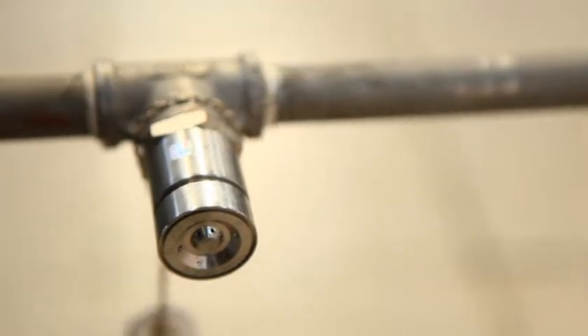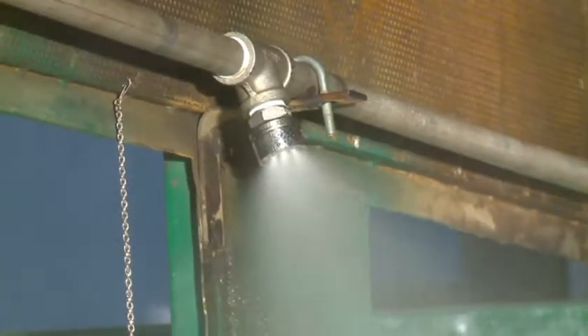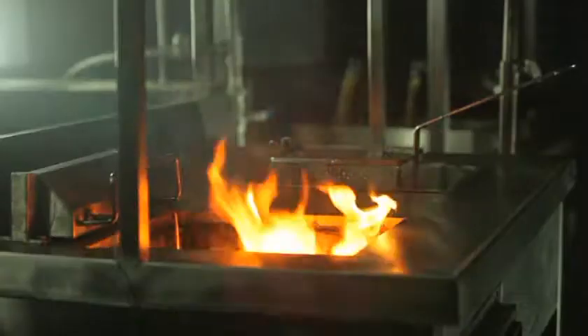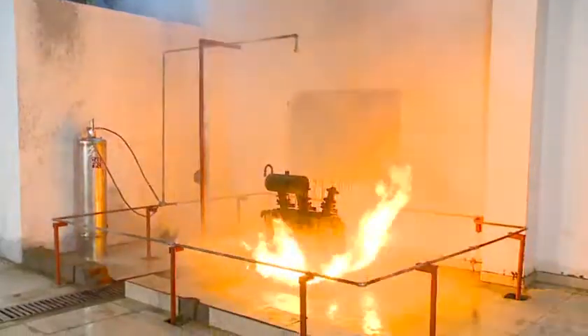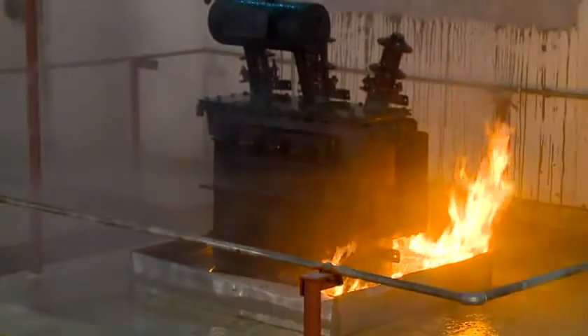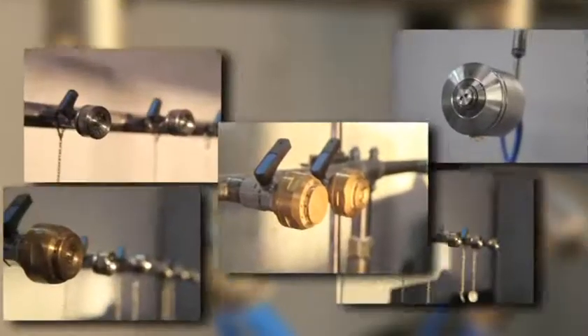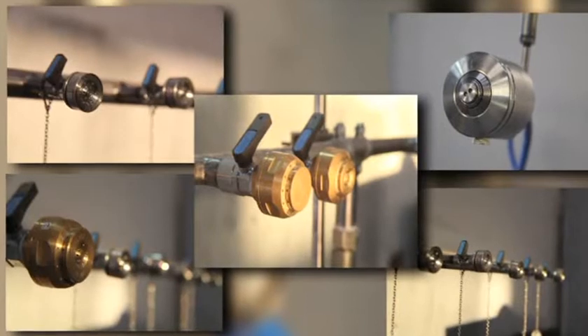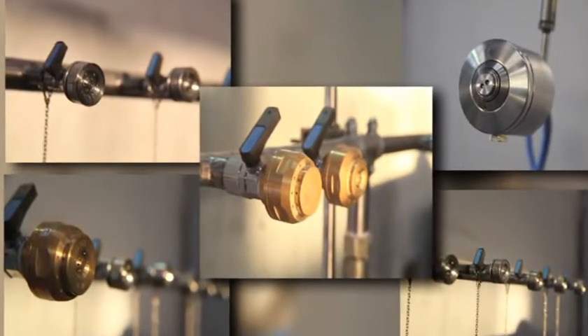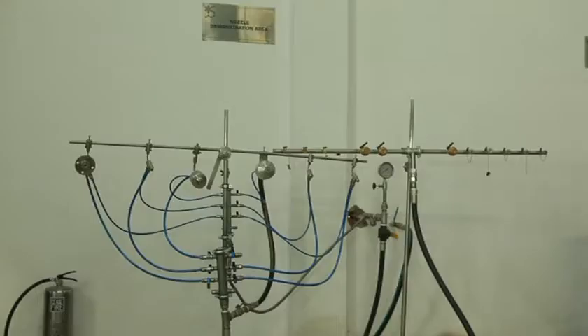Using water mist technology, we realized we could alter the very form of water, converting it into a very fine mist, thereby making it an outstanding physically acting agent with exceptionally high heat absorbing capacity due to high latent heat of vaporization. Here's how water mist works. First, water is pumped through specially designed nozzles that break water down into minuscule particles.